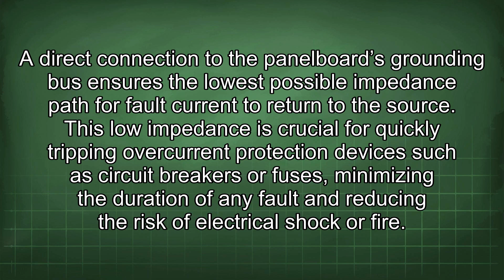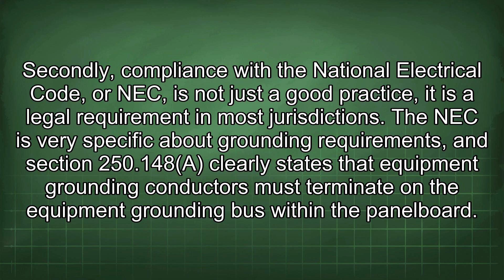Secondly, compliance with the National Electrical Code, or NEC, is not just a good practice, it is a legal requirement in most jurisdictions. The NEC is very specific about grounding requirements, and Section 250.148 clearly states that equipment grounding conductors must terminate in the equipment grounding bus within the panel board. Deviation from this requirement is a code violation and can result in failed inspections or potential safety hazards.